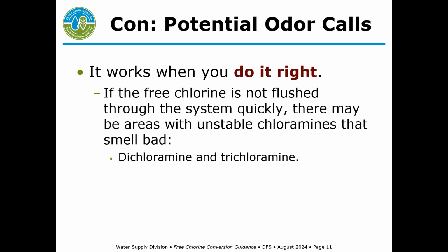Some other cons you could have: odor calls. If the free chlorine isn't flushed through the system quickly, there may be areas that have these unstable chloramines, dichloramine and trichloramine that smell bad, and you want to try to avoid that. So getting the free chlorine through quickly is probably the best way to avoid that.